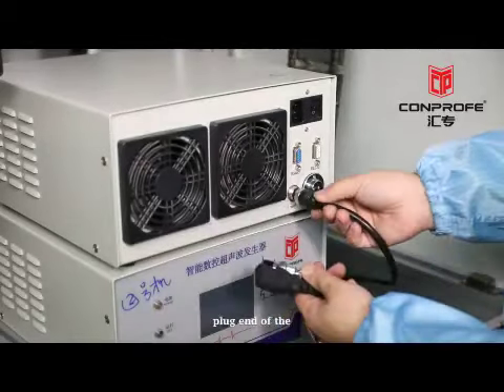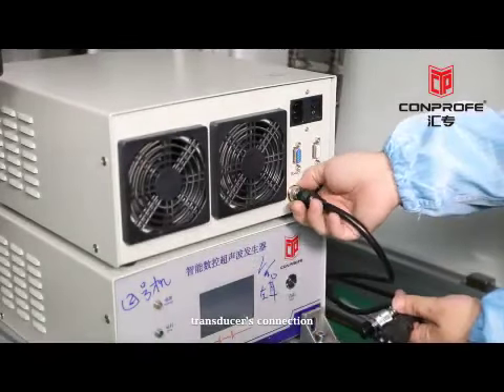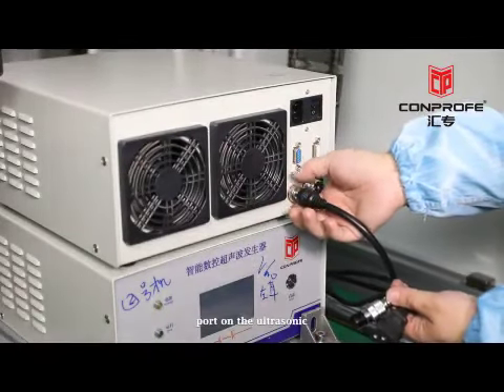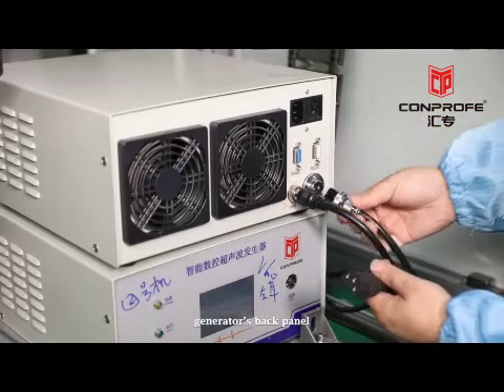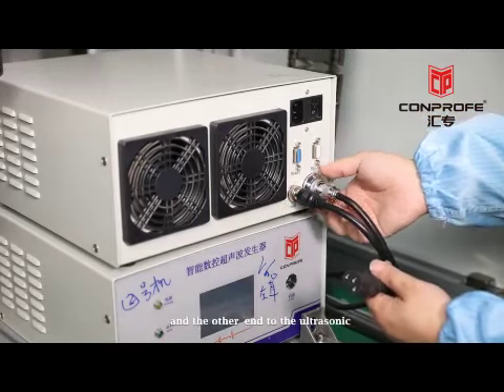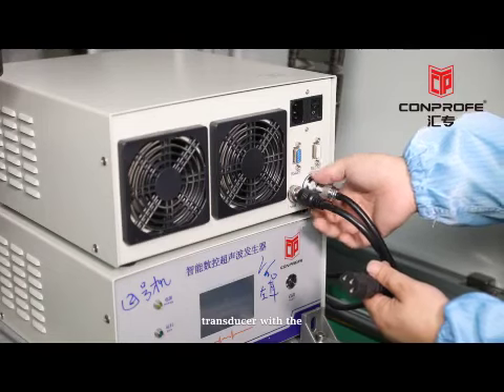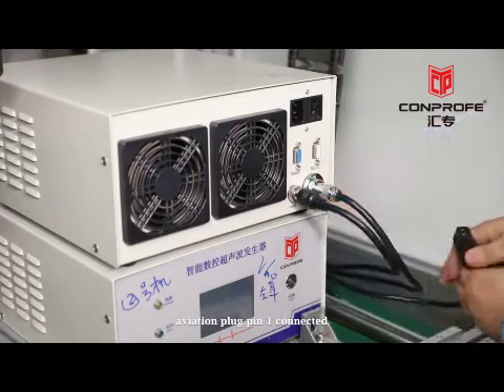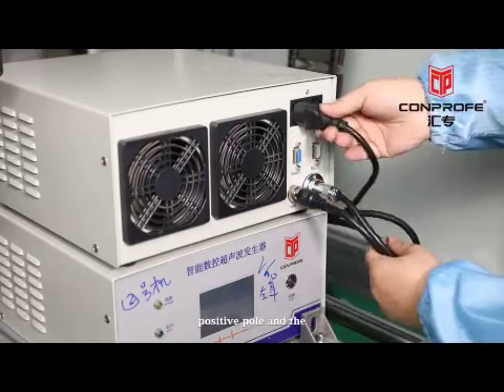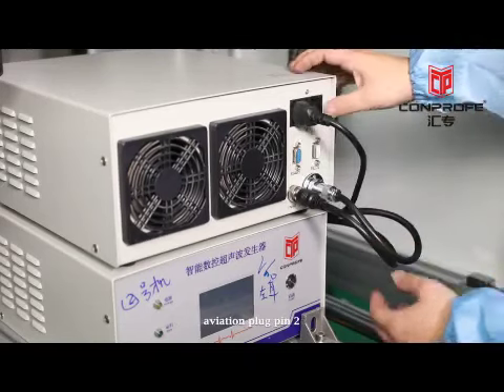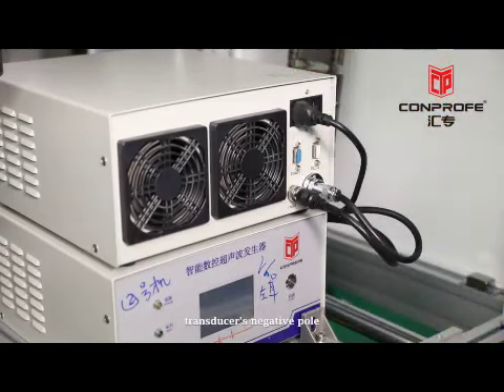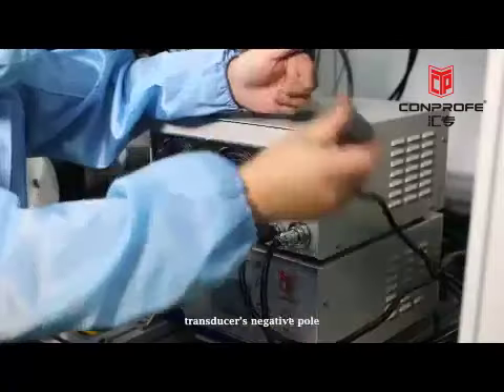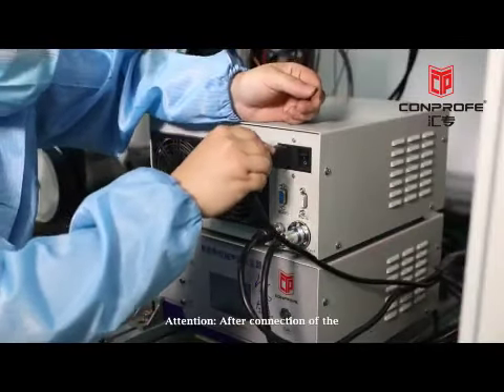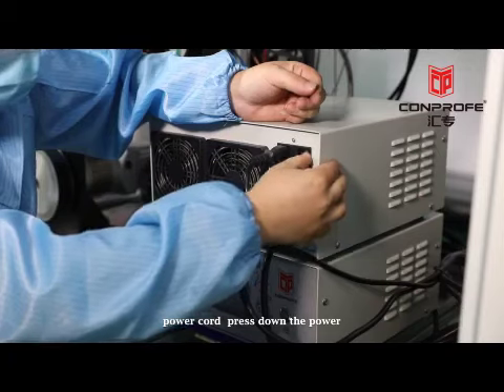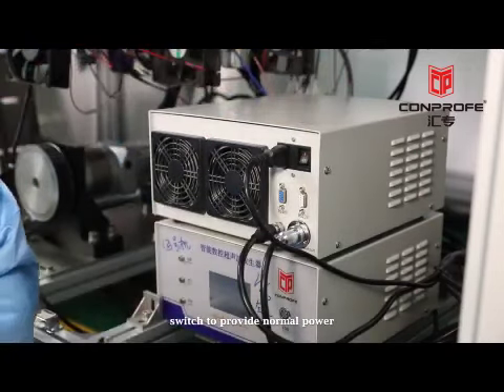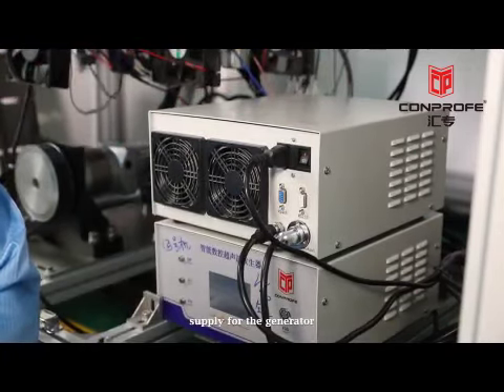Connect the aviation plug end of the transducer's connection line to the output line port on the ultrasonic generator's back panel, and the other end to the ultrasonic transducer, with the aviation plug pin 1 connected to the transducer's positive pole and the aviation plug pin 2 connected to the transducer's negative pole. Attention! After connection of the power cord, press down the power switch to provide normal power supply for the generator.